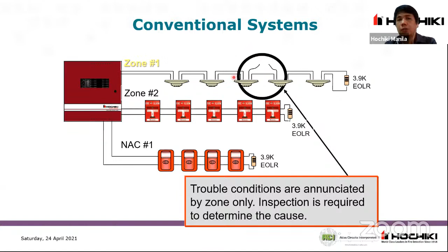So information transmitted to central station is by zone at best. Many panels send alarm, supervisory, and trouble only. So in case na magsisend tayo into a third party like BFP, so limited lang yung mabibigay nating signal sa kanila. Usually, alarm lang, supervisory, and trouble. Okay? So yun yung sa conventional natin.